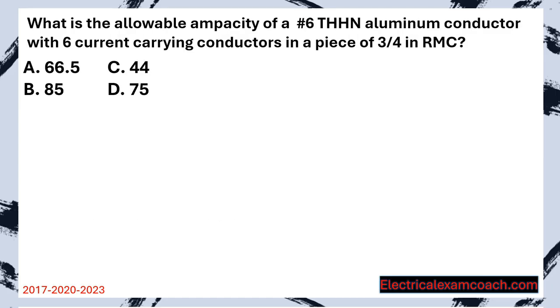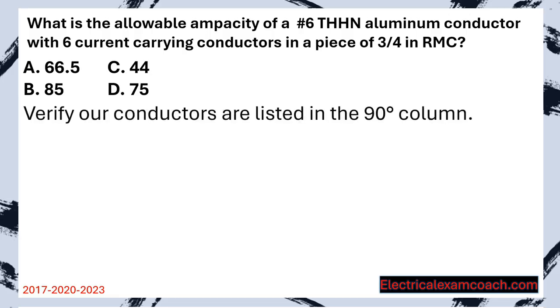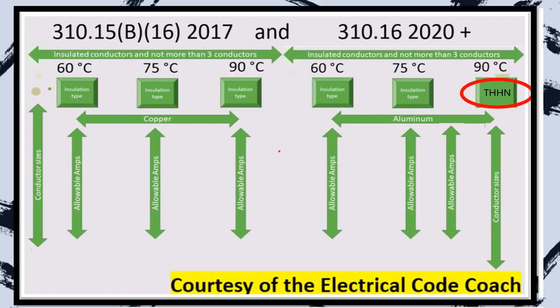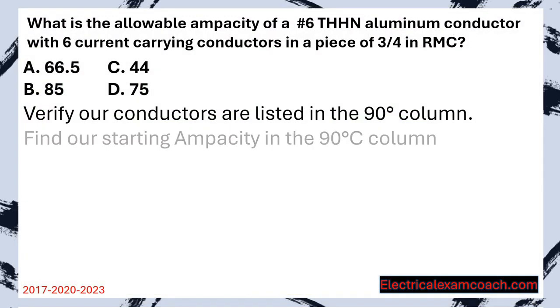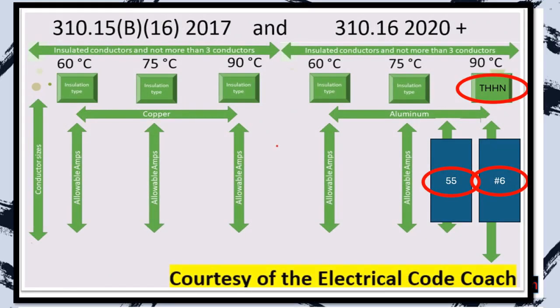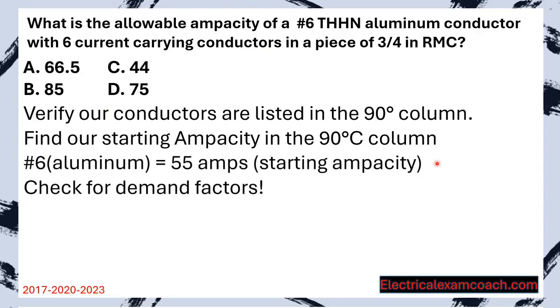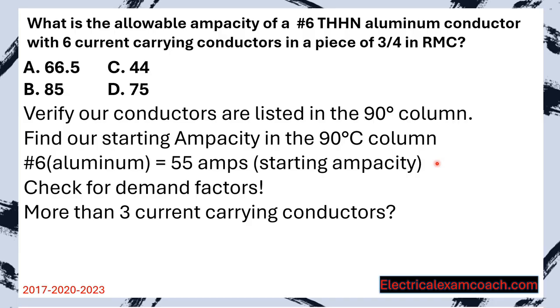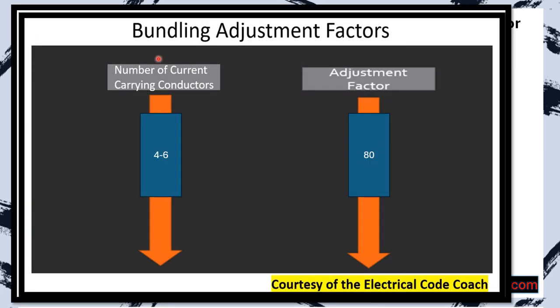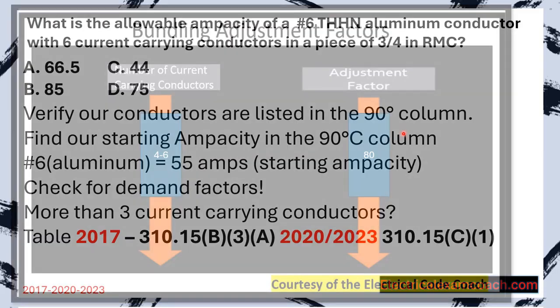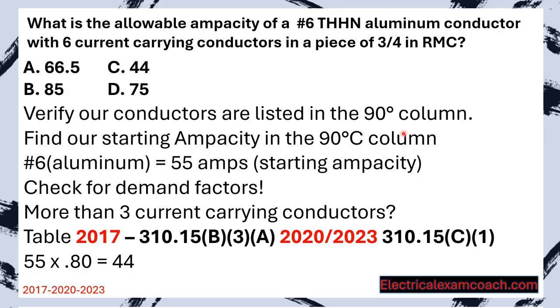Practice question: What is the allowable ampacity of a number six THHN aluminum conductor with six current carrying conductors in a piece of three-quarter inch EMT? Step one: verify THHN is in the 90 degrees C column on the aluminum side — it is. Step two: find the starting ampacity. On the aluminum side of the primary ampacity table, sliding down to number six and crossing to the 90 degrees C column gives us 55 amps. Step three: there are more than three current carrying conductors, so we head to the bundling adjustment factor table. Six conductors falls in the four-to-six range with a demand factor of 0.80. 55 amps times 0.80 gives us a new reduced allowable ampacity of 44 amps.